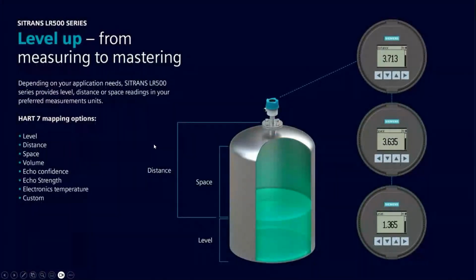Just reinforcing some of the comments they made regarding advanced diagnostics, be aware that if you're using HART, 4 to 20 with HART, and you have a HART input card, you can map a variety of different outputs from the transmitter because they're all there. And he has custom here - that would be the custom for the advanced diagnostics in his case, which would turn on or off the air purge on the LR580. So depending on what you have communication wise, you have the potential to get a lot of value, a lot of variables out of this transmitter.